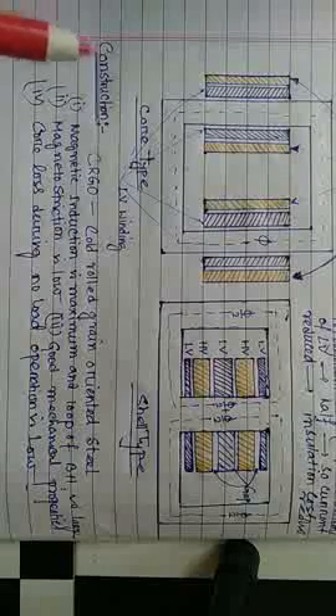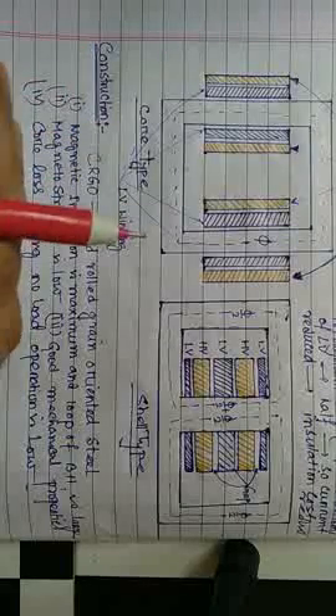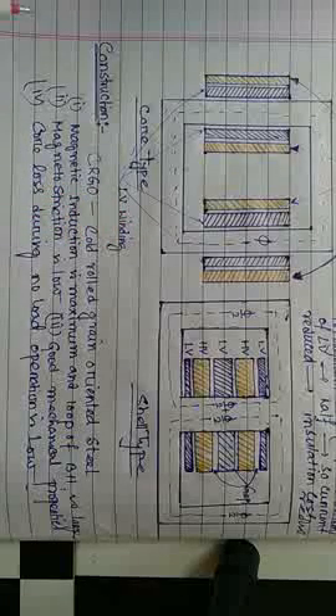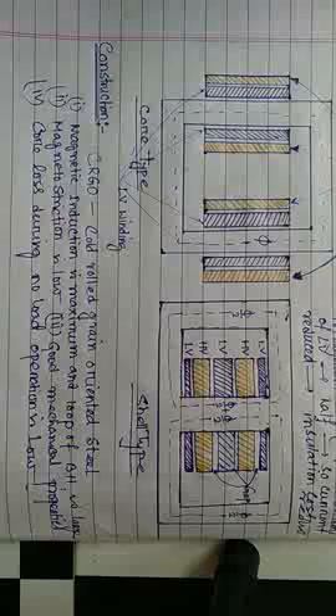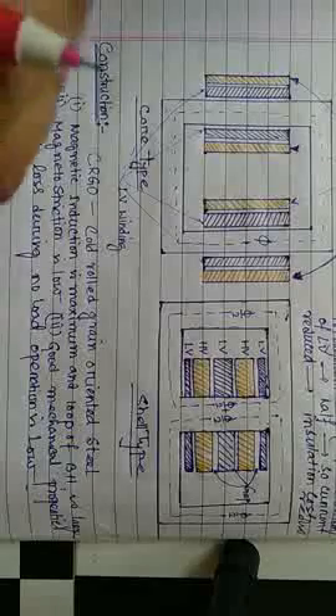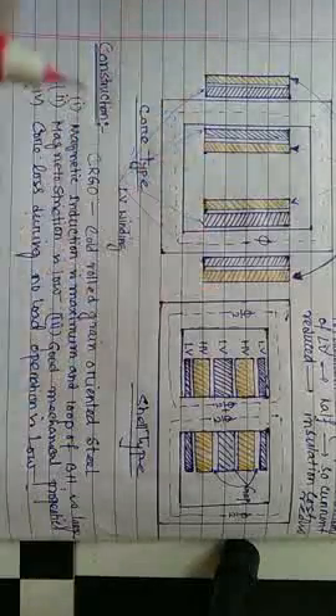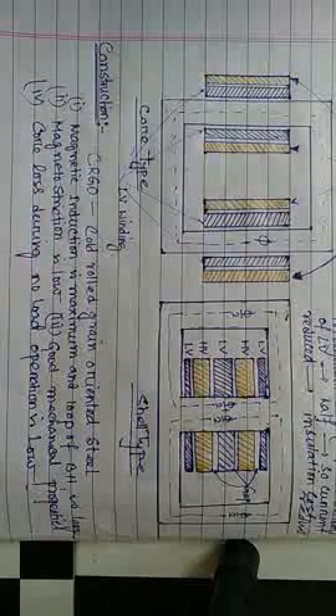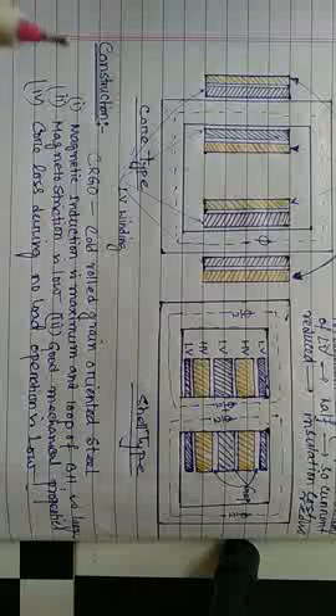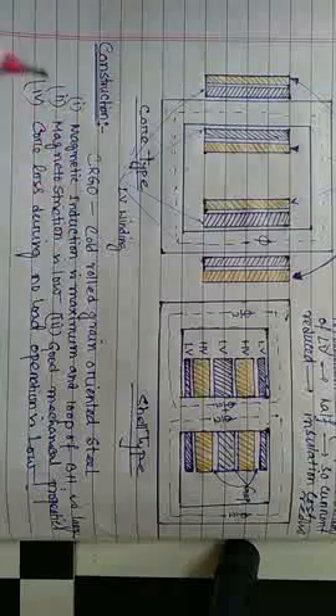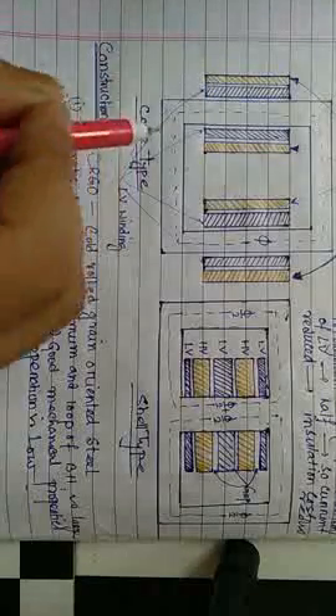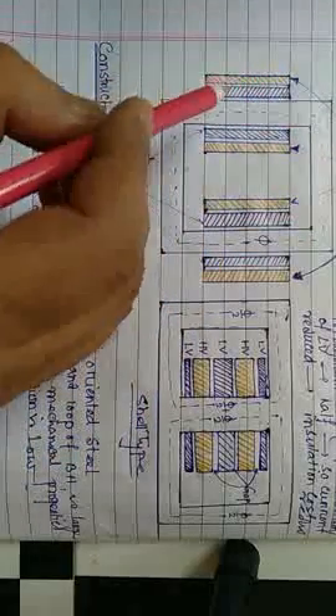Why do we use CRGO? Because CRGO, that is cold rolled grain oriented silicon steel, has maximum magnetic induction and the loop of the BH curve is small. Again, magnetostriction is very low, it has good mechanical properties, and core loss during no load operation is very low. Due to these advantages, we use CRGO material for the core.